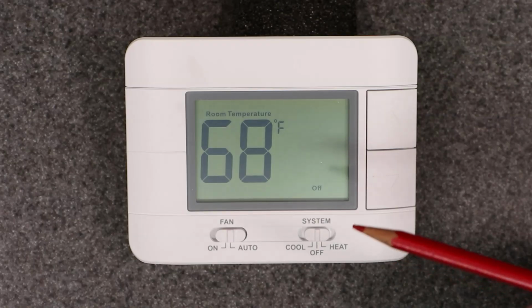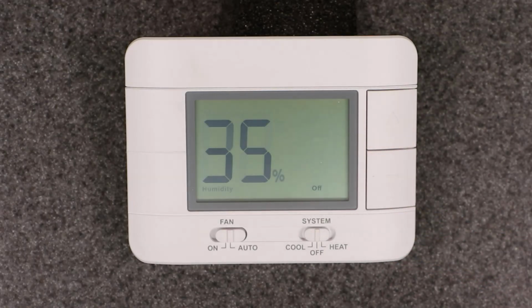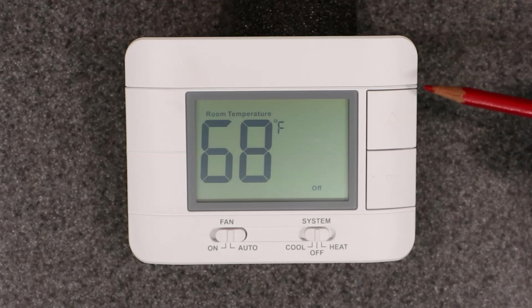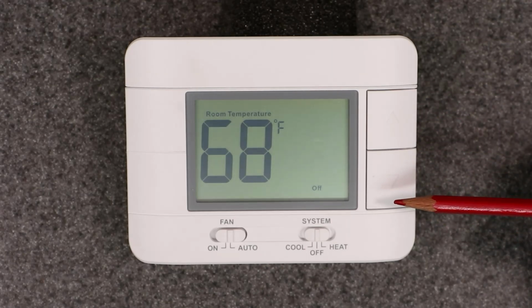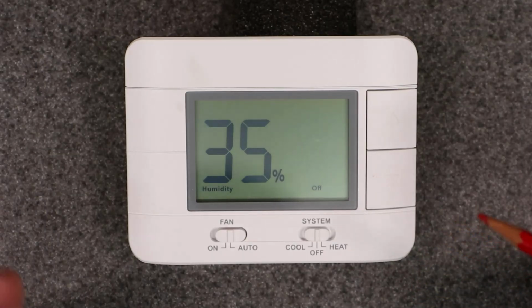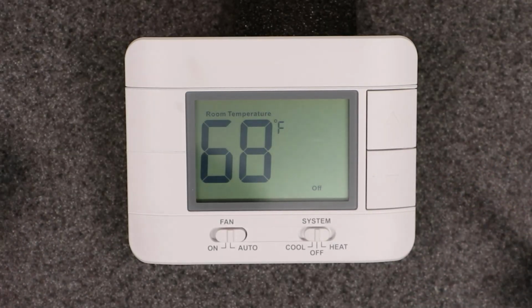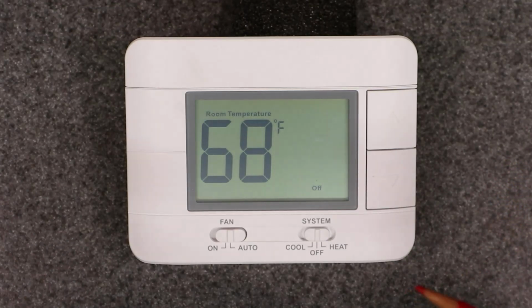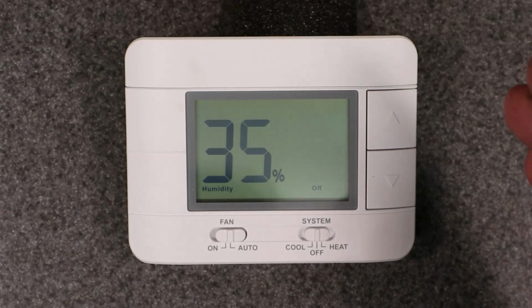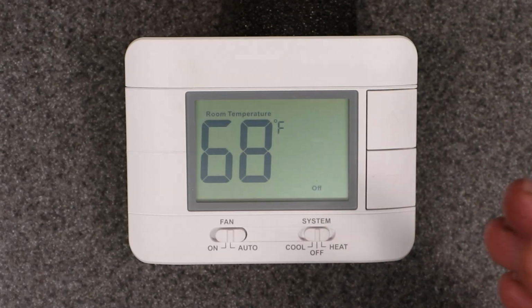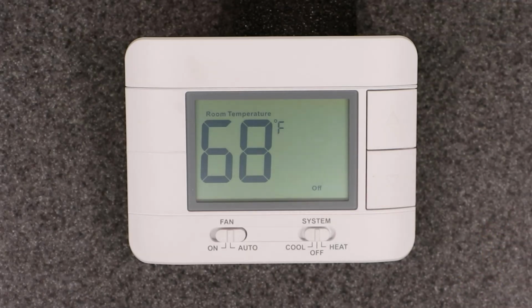This here is a single stage heating and cooling thermostat, but they also make a dual stage heating and cooling model, which is exactly the same as this. The only difference is the base plate will have more terminals for your second stage heating and cooling. So I want to do a rundown on how to operate it, what the buttons do, and a simple setup. We'll go over the back of the unit and the base plate toward the end of the video. And I want to show you a great hidden feature on this thermostat that I just don't understand why more thermostats out there don't take advantage of. But I'll get into that after I show you the function of this.